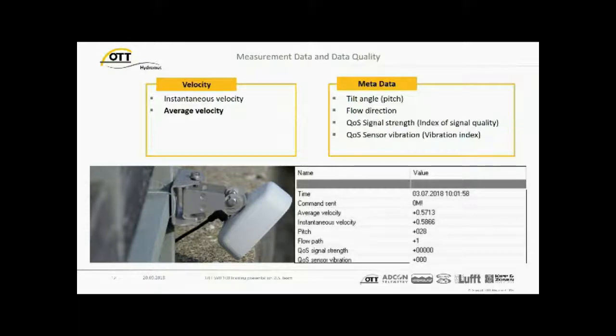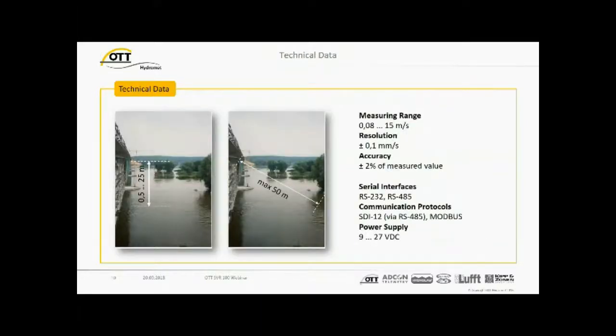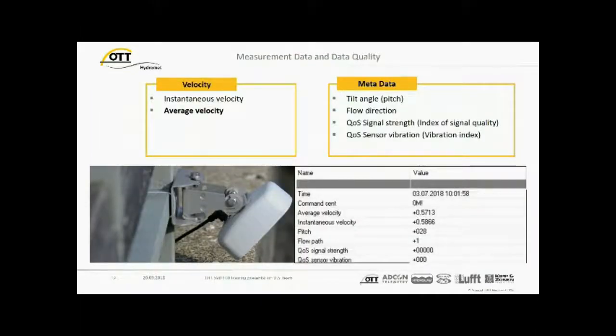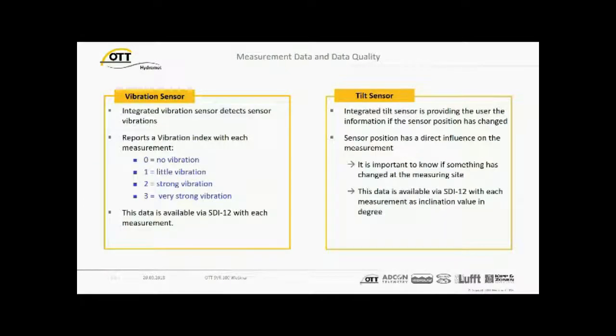You will get an index of signal quality. That means QoS is the signal strength index, with values 0, 1, 2, and 3. And you also get a vibration index, because if the sensor starts to vibrate, this also affects the accuracy of the measured velocities, because it has a shift effect. You see here in this line different times and the command sent, the SDI command, average velocity, instantaneous value, pitch, flow path, and both the signal strength and sensor vibration index values.